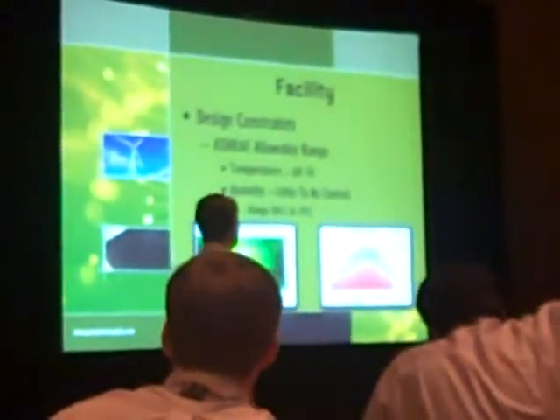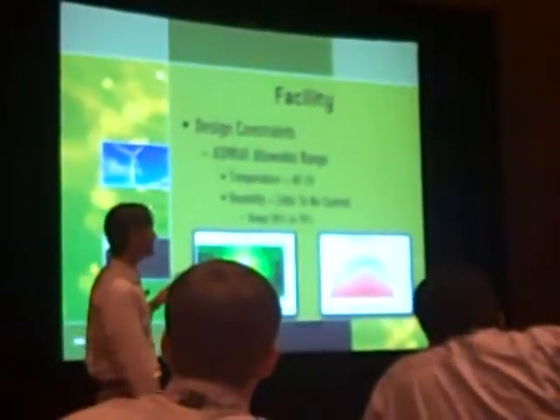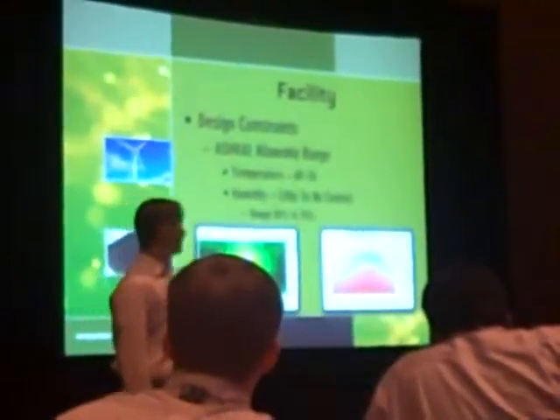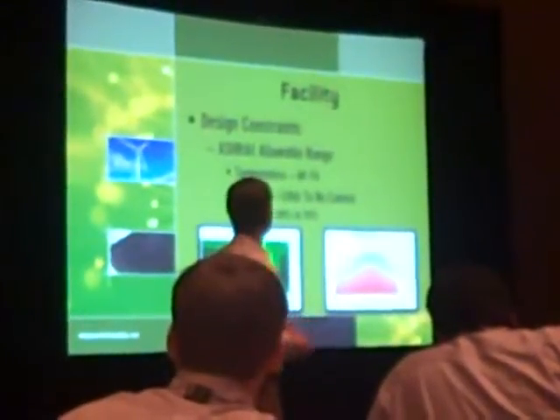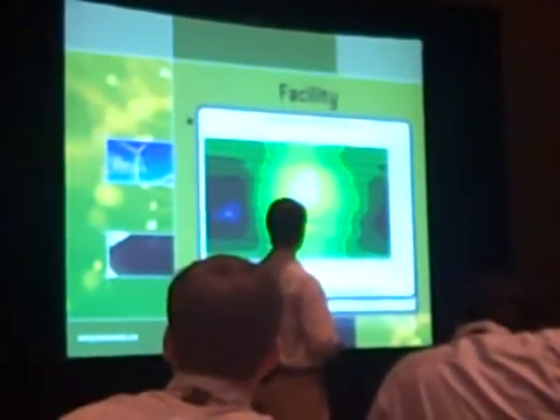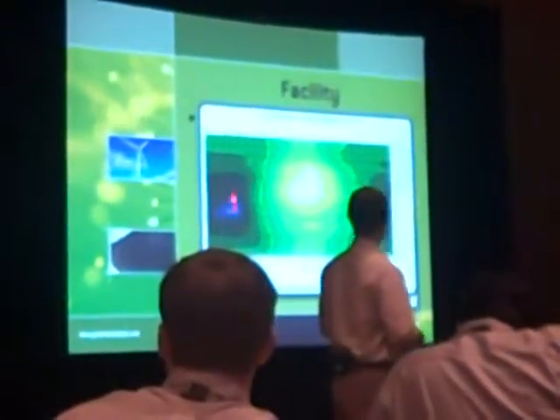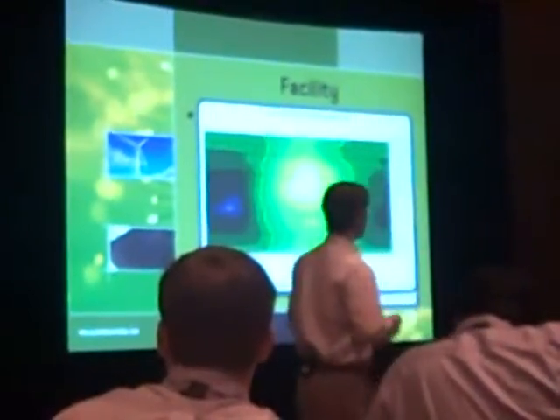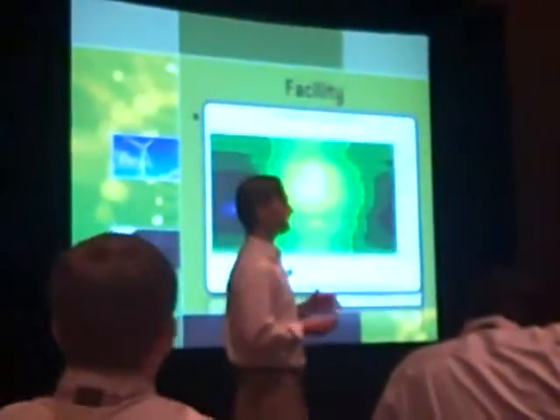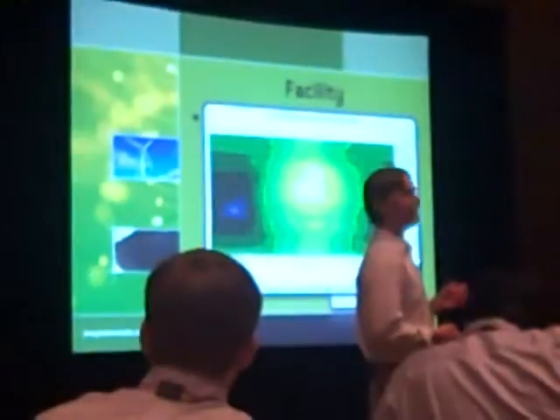So from a facility perspective, we did have design constraints. We have chosen to go by ASHRAE's allowable range, specifically 69 to 74 degrees. We are fortunate that we only have to have little to no humidity control in our data center. This is a graph of hourly relative humidity in the Cheyenne region. The minimum humidity level that we see in Cheyenne is at 33%, with the maximum sitting at about 71%. So there are peaks and valleys where we have to manage humidity, but we are able to avoid the vast majority of the costs associated with humidifying, in our case, the data center.